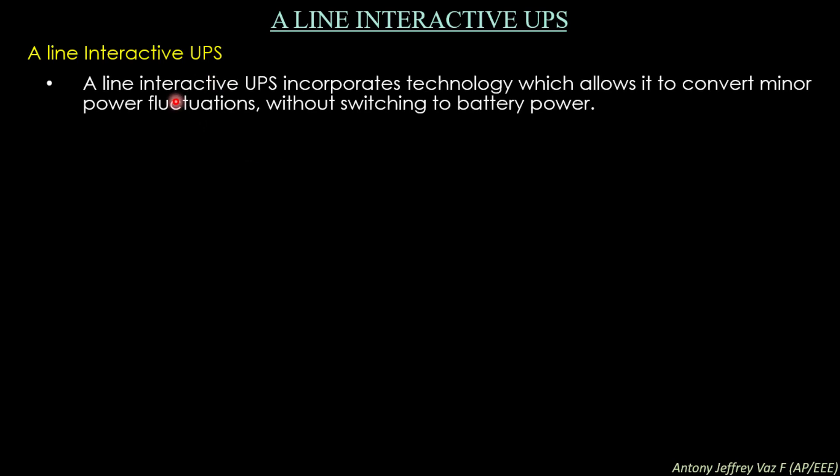The next type is the line interactive UPS. This incorporates technology that allows it to correct minor power fluctuations without switching to battery power. Unlike standby UPS, which immediately switches from AC to DC battery power upon any low voltage or fluctuation, the line interactive UPS corrects the AC line voltage at the input and delivers it to the output device at the required level.